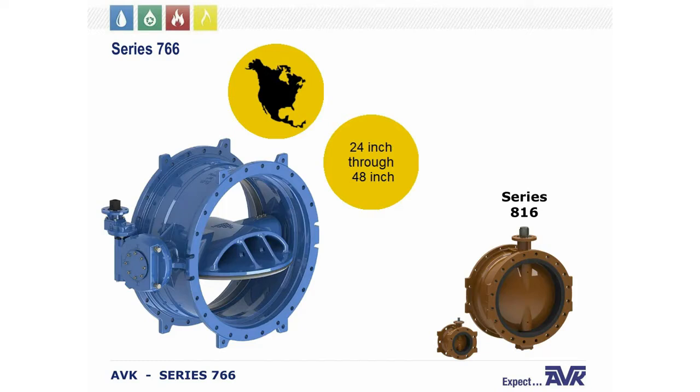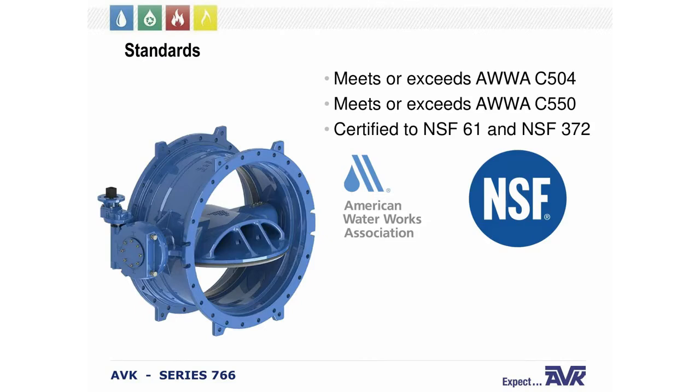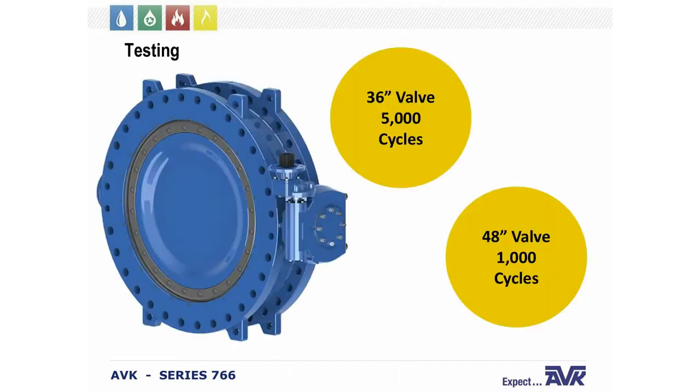We also have smaller ones in our Series 816. The main function of the butterfly valve is to shut off the flow of water. The 766 meets and exceeds AWWA C504 and C550 as well. We are certified NSF 61 and 372 for the Safe Drinking Water Act. In testing, we run 36 inch valves at 5,000 cycles and 48 inch at 1,000 cycles, with 250 PSI of unbalanced pressure — putting a lot of torque on the valve. The 766 had no issues or leaks through these tests.